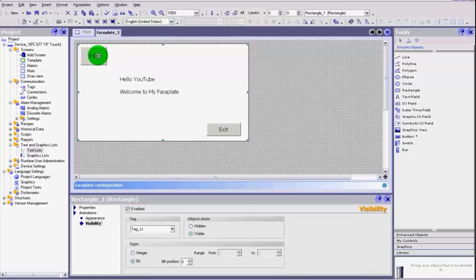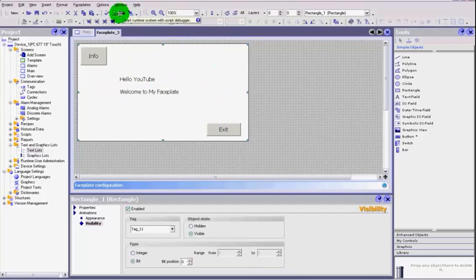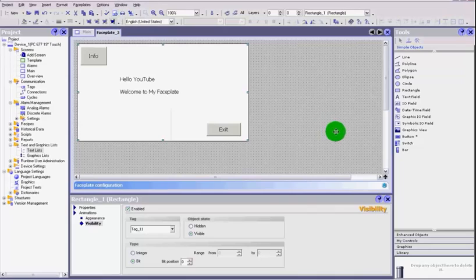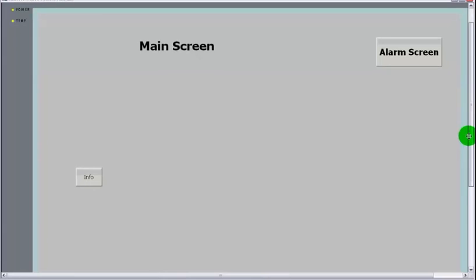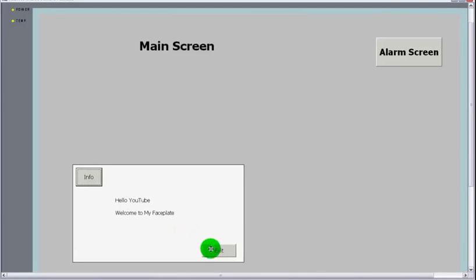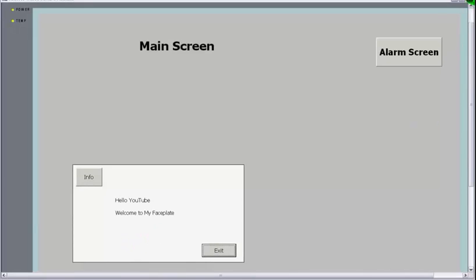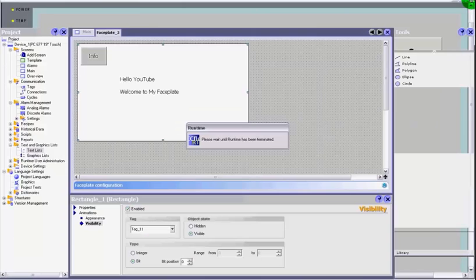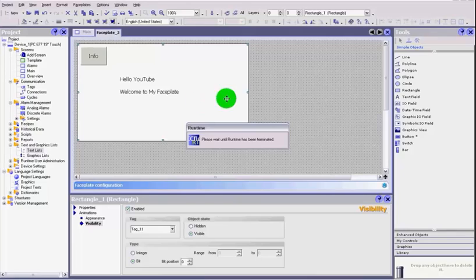So now only when we hit that button on the screen and that bit goes high do we show these other objects on the screen. Let's try and make sure that works correctly. You'll notice now that everything else has disappeared except our button. When we click the info button, the faceplate appears and it gives us our message, our button, and our rectangle. Now we haven't set the exit button to do anything yet.